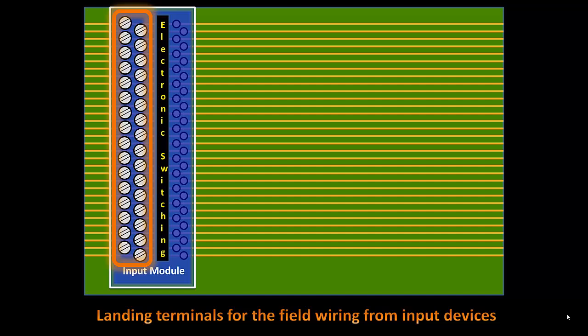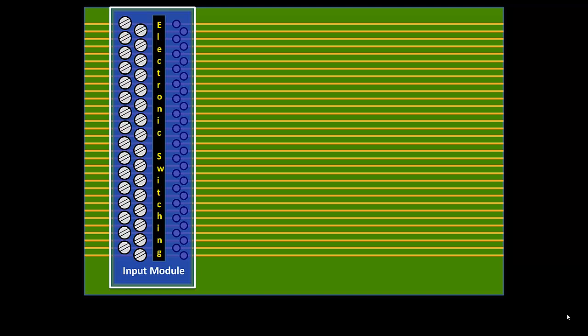These landing terminals are for landing the field wiring from input devices — photo eyes, push buttons, limit switches. You'll typically have a common voltage connection going to all the devices. This is our input module: it inserts electrical influences from the outside into the backplane to control the electrical state of the copper traces. We're not using a battery here, but we're still using EMF — electromotive force — to change the state of the copper traces on the backplane.